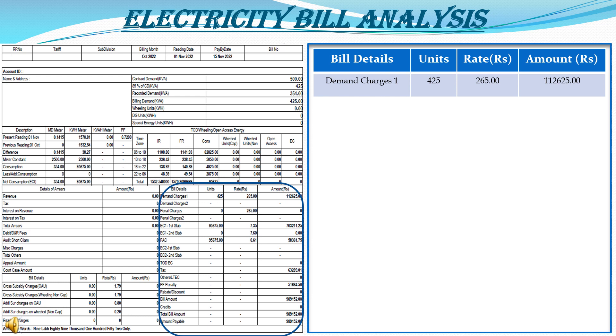Now the electricity bill calculation section. The first section is demand charges. The units are mentioned as 425 KVA because the contract demand is 500 KVA and the electricity company charges 85% of contract demand, which is 425 KVA. The rate per unit is 265 rupees per KVA. So 425 multiplied by 265 gives a total amount of 1,12,625 rupees. This is a fixed charge every month — whether you use electricity or not, you have to pay 1,12,625 rupees because you applied for 500 KVA as contract demand.